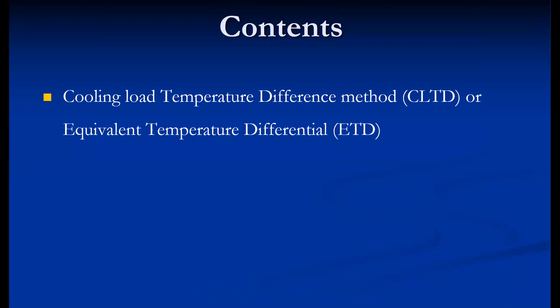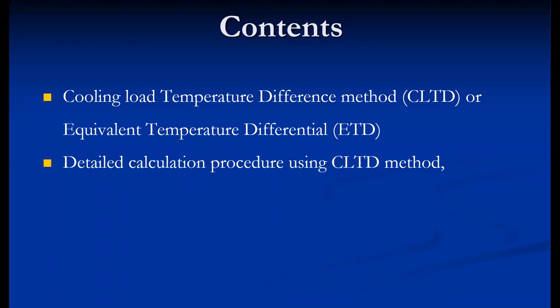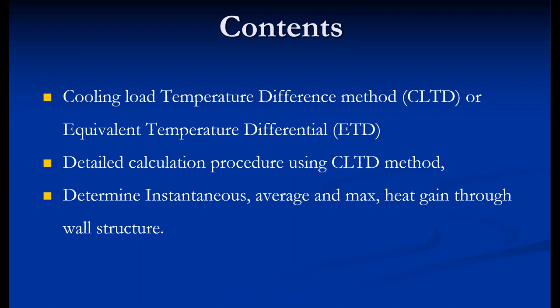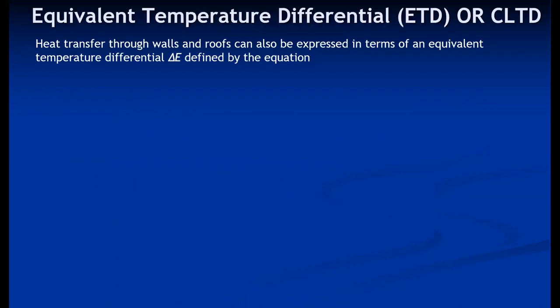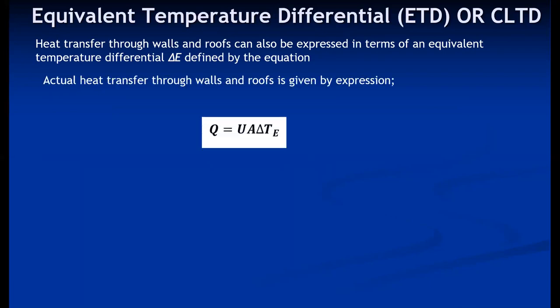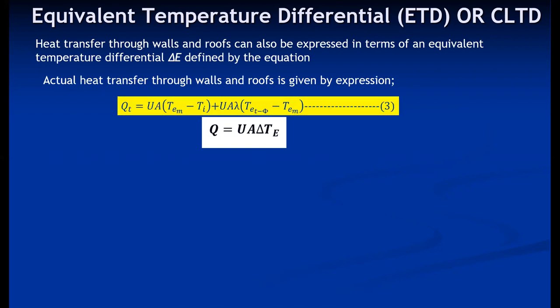We will mainly discuss the CLTD, or Cooling Load Temperature Differential method. The detail calculation procedure, the conditions used for calculating delta T, heat transfer to walls and roofs can be expressed in terms of an equivalent temperature differential delta T, defined by the equation q equals UA·delta T. The actual heat transfer to walls and roofs is given by the expression discussed in the previous method using decrement factor and time lag.